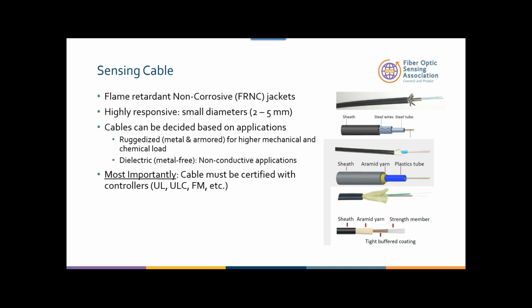In the case of fiber optic linear detection, we have definitely a flame retardant FRNC jacket, highly responsive small diameter system. So we really want a system that says, I am detecting the fire or a temperature change or an event as fast as possible. So most of the time you get a cable that has a response time that's as fast as you can get. So at the end of the day, we have a ruggedized cable, we have a dielectric cable. They meet existing UL, ULC and FM ratings. These cables are rated in such a way that they can sustain certain temperatures, at least up to 900, 950 degrees Celsius, and survive and tell you exactly what's going on with the fiber.